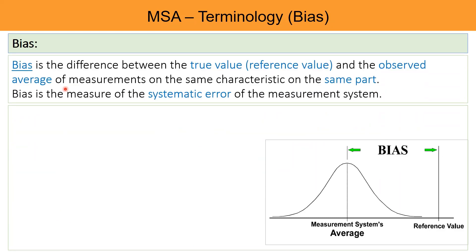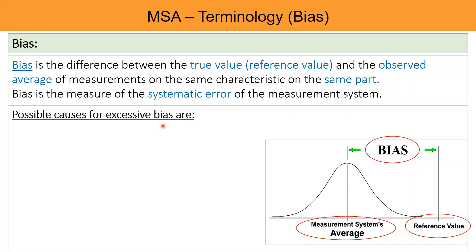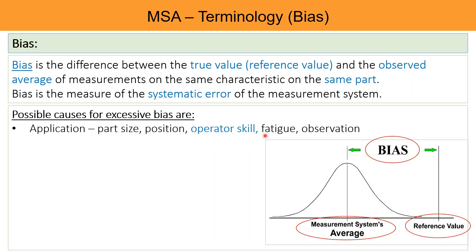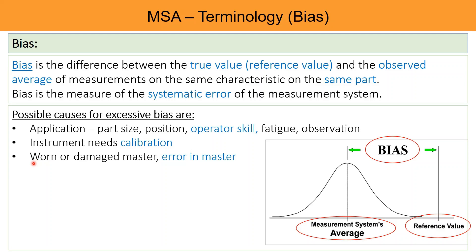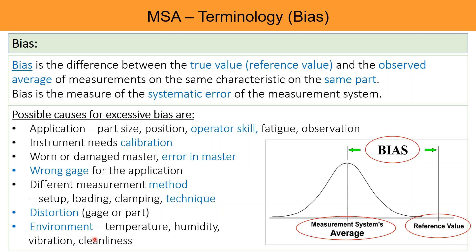Bias is the difference between the true value or reference value and the observed average of measurements on the same characteristics on the same part. Bias is the measure of the systematic error of the measurement system. Possible causes for excessive bias include part size, position, operator skill, fatigue, instrument needing calibration, worn or damaged master or error in the master itself, wrong gauge for the application, different measurement methods, setup or loading or clamping techniques, distortion of the gauge or part, and environmental conditions like temperature, humidity, vibrations, and cleanliness.